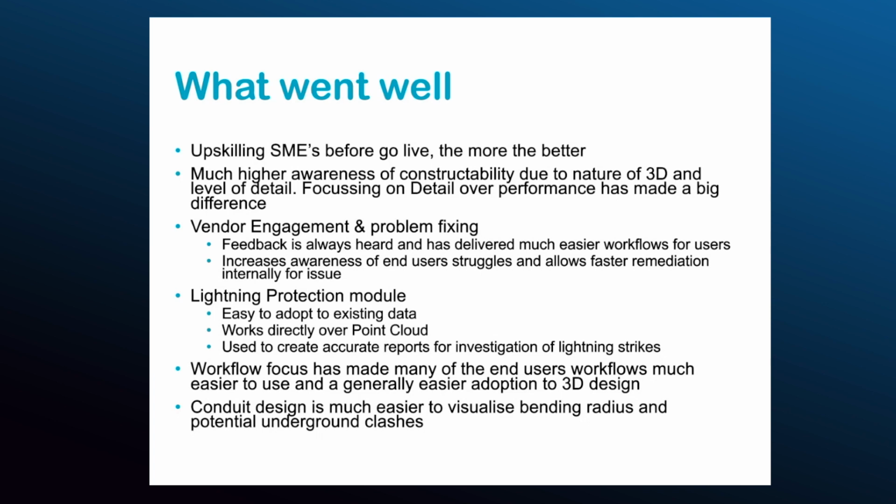The last thing that also sits into a few places is our conduit design. So something that really became apparent very quickly is how much easier it is to visualize a conduit in 3D versus 2D, and where you start seeing issues with things like bending radiuses, underground clashes. So being able to do full conduit networks in 3D became hugely beneficial to some of our on-site construction issues.